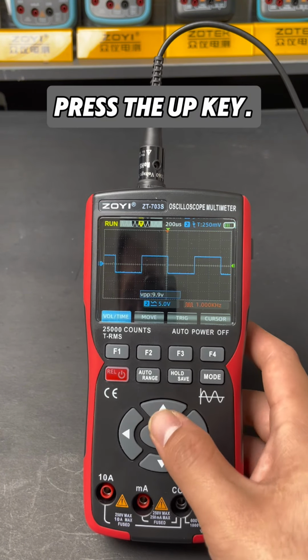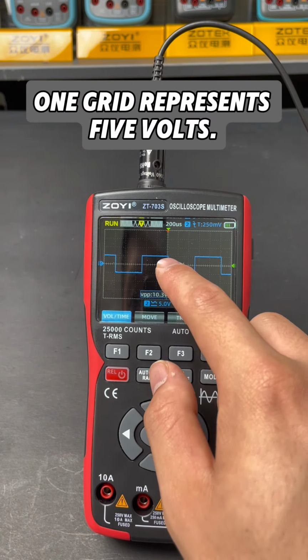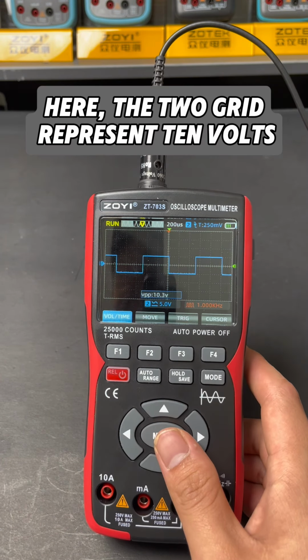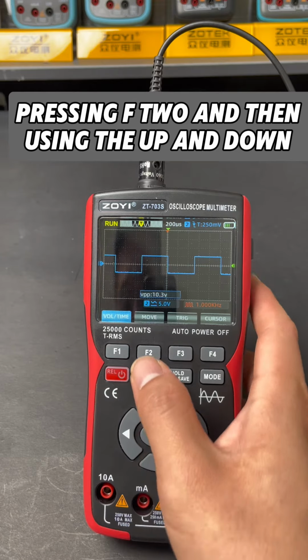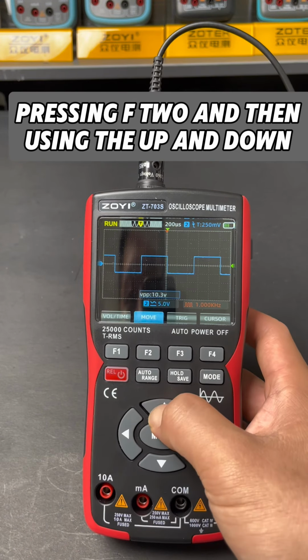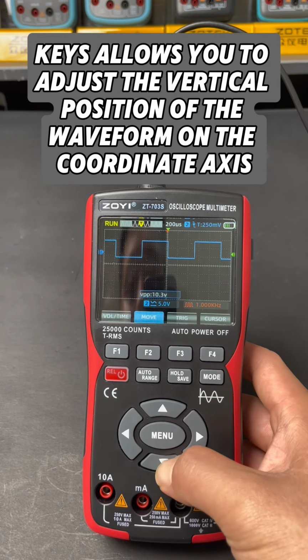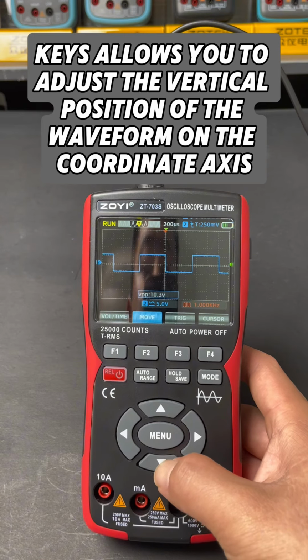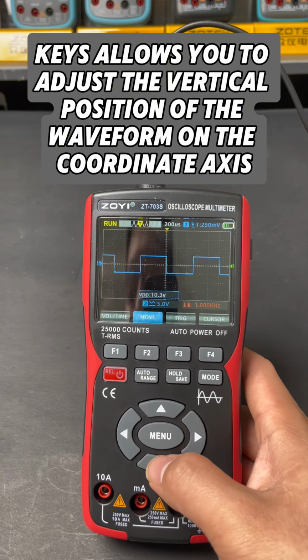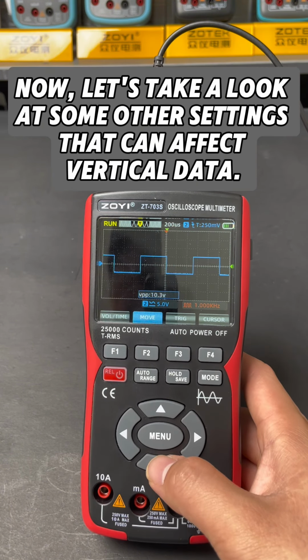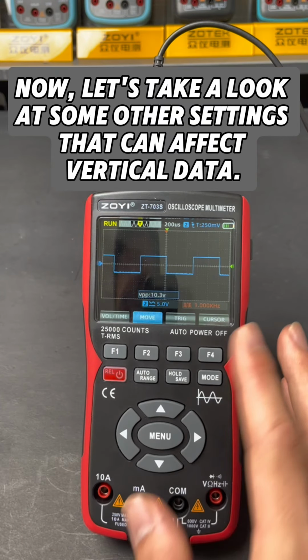Press the up key. One grid represents 5 volts. Here, the 2 grids represent 10 volts. Pressing F2 and then using the up and down keys allows you to adjust the vertical position of the waveform on the coordinate axis. Now, let's take a look at some other settings that can affect vertical data.